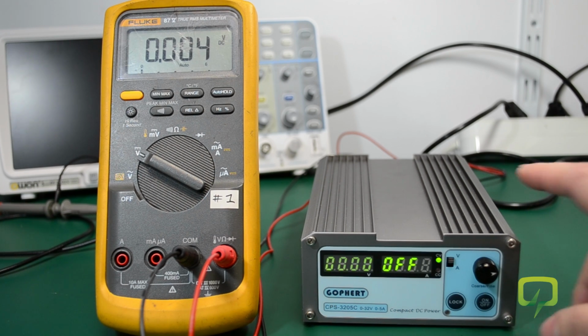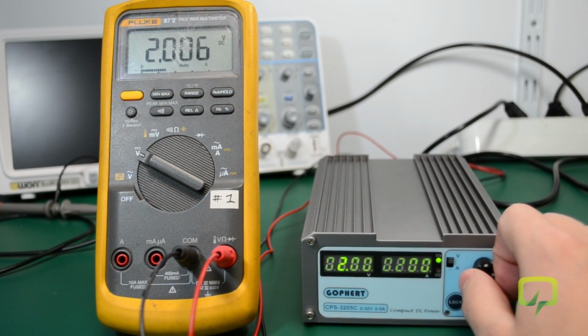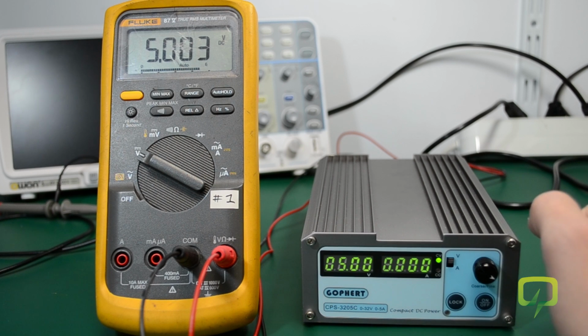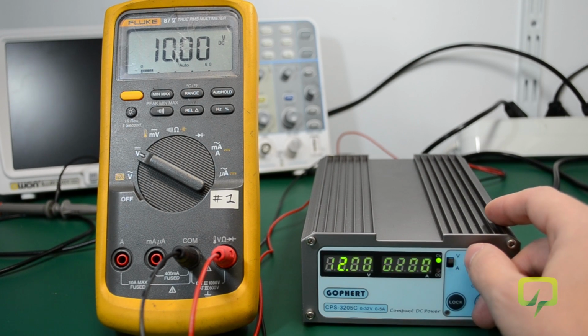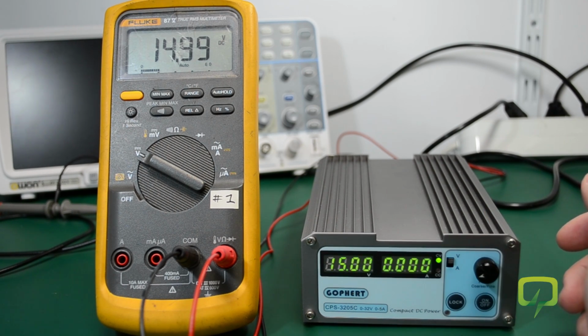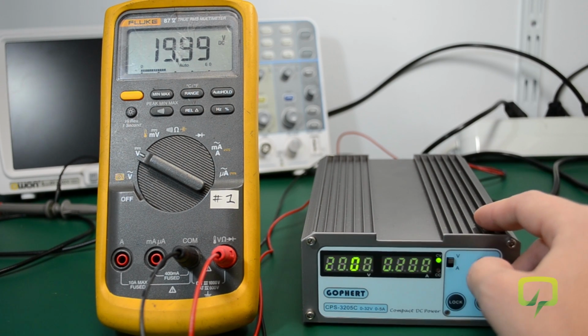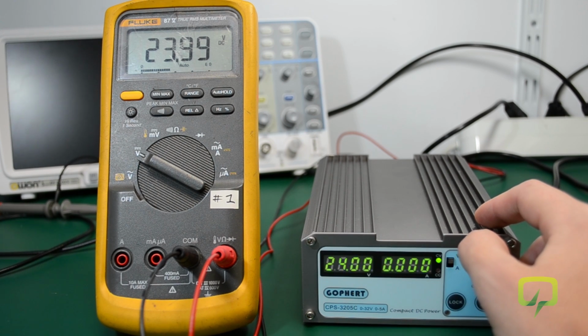So let's start with the voltmeter. I'm going to turn the power supply on. The power supply is set to 2 volts and the Fluke 87 agrees. Now let's adjust the voltage to different levels. 5 volts, perfect. 10 volts, the Fluke 87 agrees. 15 volts, yeah, no problem. That's 20 volts, the Fluke 87 once again, it's almost spot on. If I give it some time to stabilize the measurement, or maybe stabilize the power supply regulation, it matches perfectly. Let's go to 24 volts, yeah, once again, no problem.